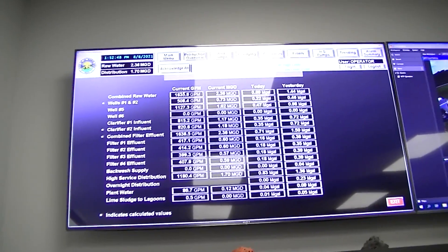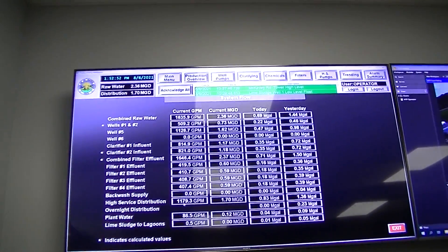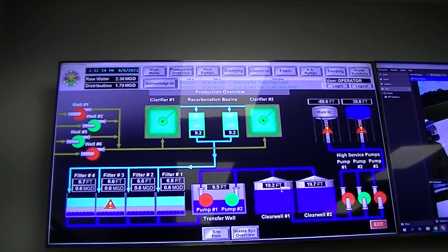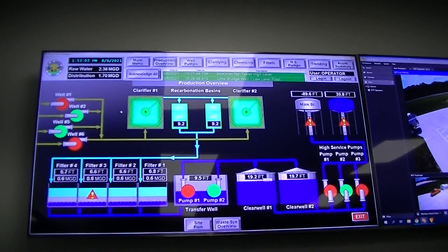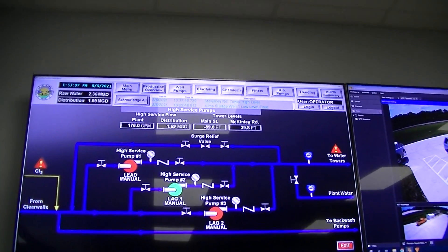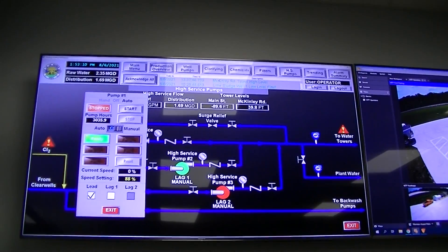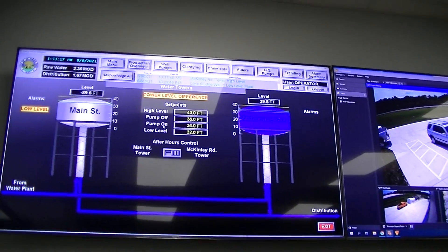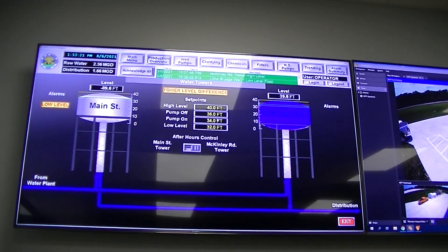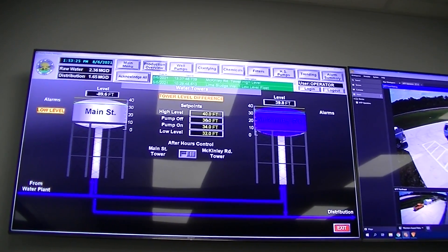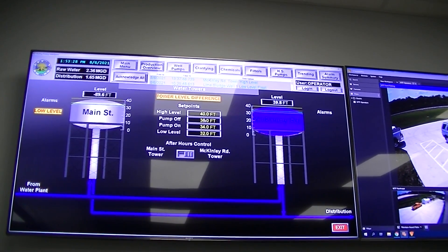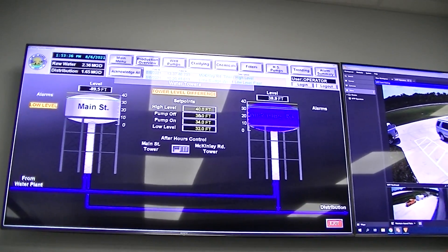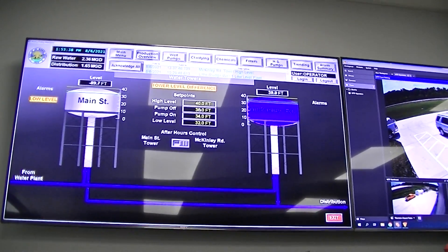We're currently running 1,600 gallons a minute in, and 1,180 gallons out. So basically we're going to work on filling these guys up now. Overnight at shutdown, the last shift guy comes here and all he does is put the pump into auto. It's programmed so that when the tower drops down to 34 feet, that's when that pump's going to kick on — it'll pull from your clear wells and fill it up to 36 feet, then turn off. Because we want to get those towers to drain down some so we can put more fresh water in. If you're always full, you could run into a stale water situation.